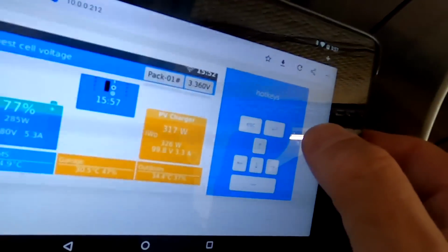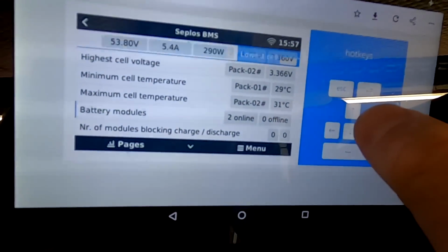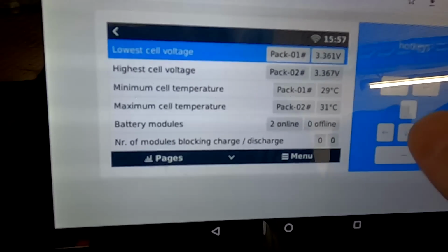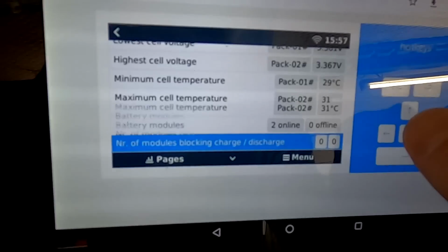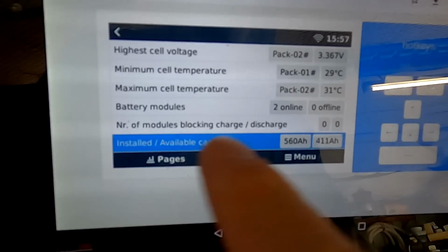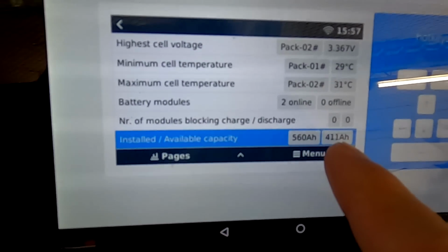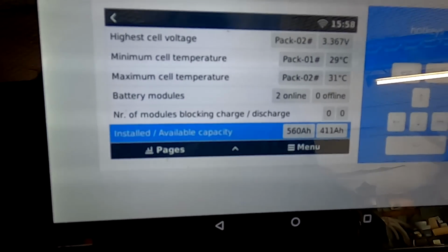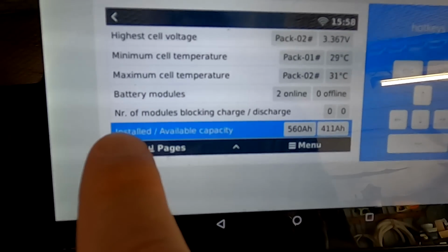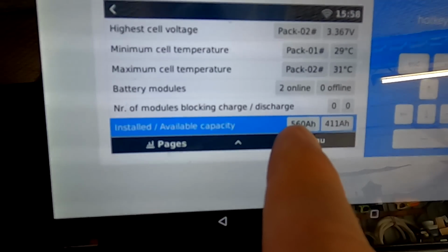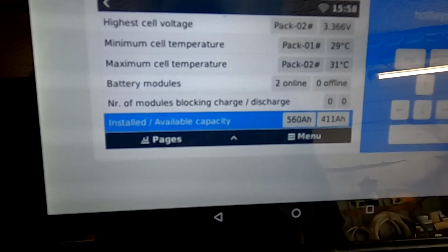In the Victron system, when we go to the 2 online, 0 offline, that's fine. And here all the way down, it gives us 560 ampere hours installed, 411 ampere hours usable. And this is not even correct here. Installed, we don't have 560 ampere hours installed, because the master battery is a 280 ampere hour rated battery. It thinks, because we have 2 batteries, it's 560.